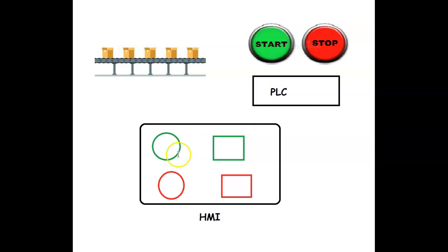Well, we've got to modify our program to allow for these virtual buttons. Now, these virtual buttons are nothing more than a signal being sent to the PLC. So they're going to use a status bit address. And if you remember from your data tables, your status bit addresses are the B3 file area. Now, these lamp indicators here are going to look at the data table for outputs. So they're going to go look at the output data table, which is the letter O, and the corresponding real-world address for these output lamps, not the buttons, the lamps.